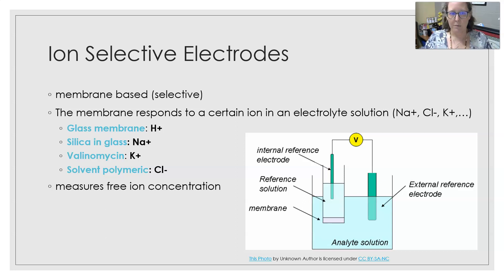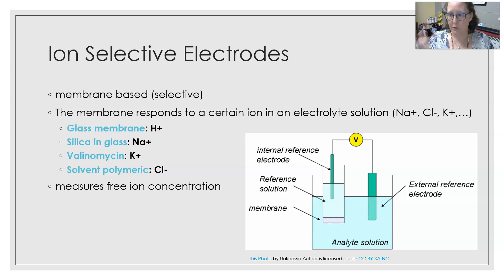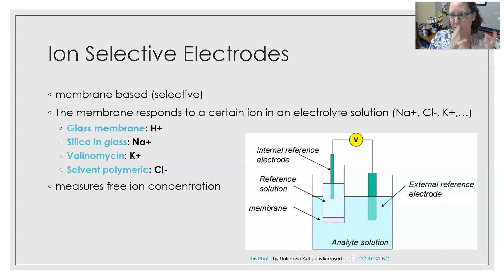So if you want to measure sodium, potassium, and chloride in a sample, you would have three electrodes — three ISEs. The first one would be specific for sodium and would measure sodium. Then the sample would go to the next one, which would measure potassium. And then to the next one, which would measure chloride. You would get all your results and they would be sent over to the computer.